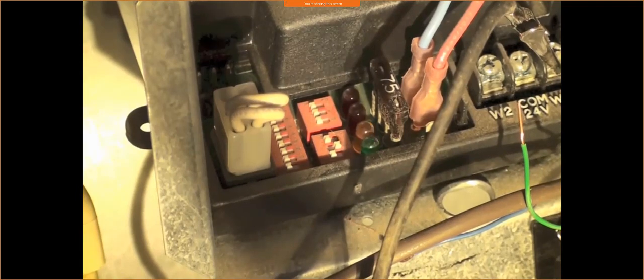All right, this fault here is a pressure switch problem fault. Now, if the pressure switch doesn't close within a few seconds of the inducer coming on, you're going to get this code. Or if the pressure switch is stuck closed, you'll get this code. This is one of the most common codes we have, and it's usually not a pressure switch problem. It's usually a venting problem, like a sagging vent, water in the vent, plugged vent blockages, or condensate blockages where your condensate drain is plugged. Those are all things that can cause this. The pressure switch could be the problem, but it probably isn't. So that's pressure switch problem.